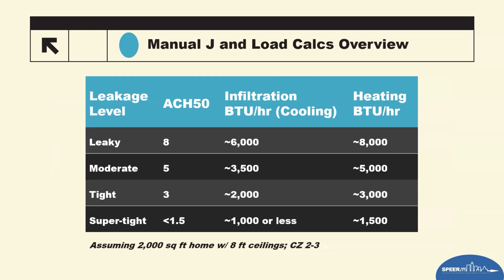And of course, we've always talked about this multiple times. Anytime we talk about HVAC, we always go through the Manual J and S. That never gets old, saying that. They are required by code and they must be collected and verified for today's types of building construction. So Manual J isn't any good unless you also collect Manual S to compare the BTU output of the equipment to the BTU of the loads that have been calculated by the Manual J.